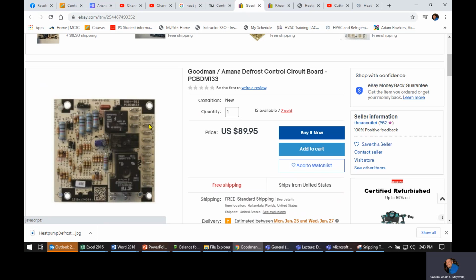Is your common coming to it, and CRV is common from the reversing valve. So the reversing valve actually has 3 different hookups. You've got orange coming in from the stat, through the board, depending on if it's calling or not. O comes back out, goes to the defrost or goes through the board to the reversing valve, through the coil, back on common, right? So we can draw this out when we get in class, but hopefully you get a little bit of what I'm saying.